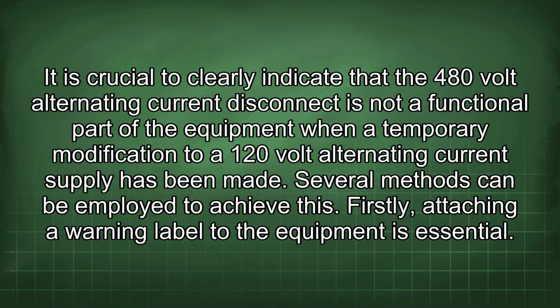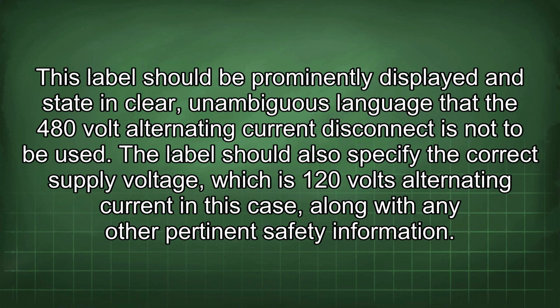It is crucial to clearly indicate that the 480-volt alternating current disconnect is not a functional part of the equipment when a temporary modification to a 120-volt alternating current supply has been made. Several methods can be employed to achieve this. Firstly, attaching a warning label to the equipment is essential. This label should be prominently displayed and state in clear, unambiguous language that the 480-volt alternating current disconnect is not to be used. The label should also specify the correct supply voltage, which is 120 volts alternating current in this case, along with any other pertinent safety information.